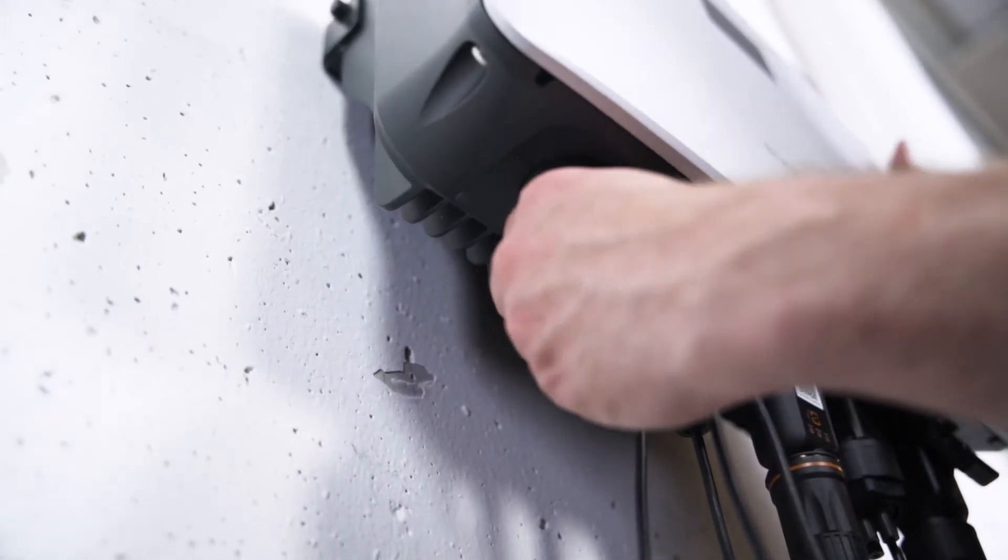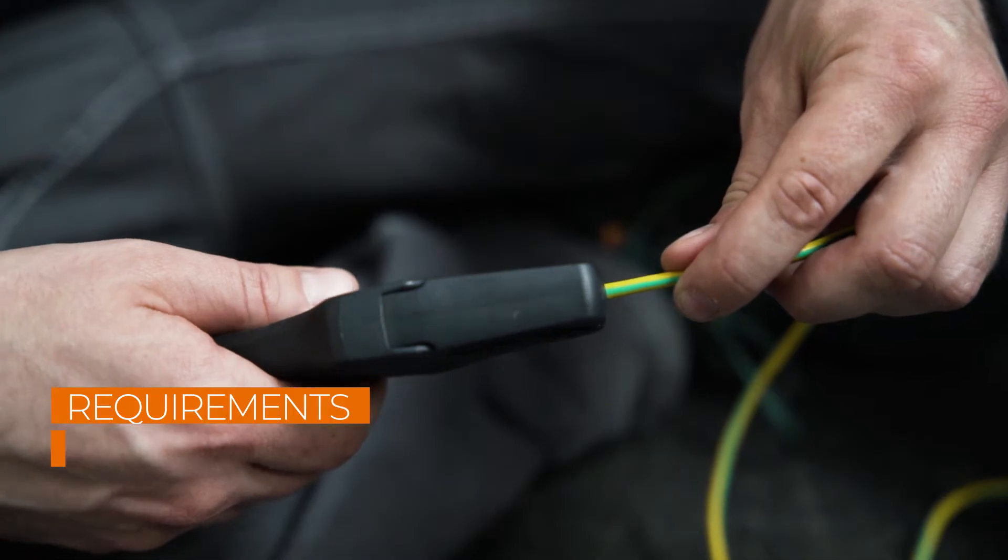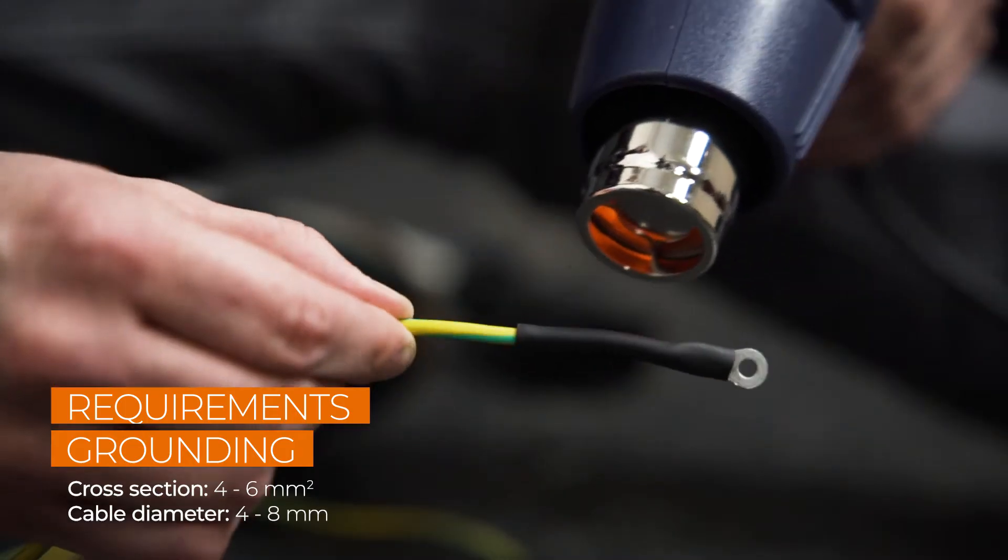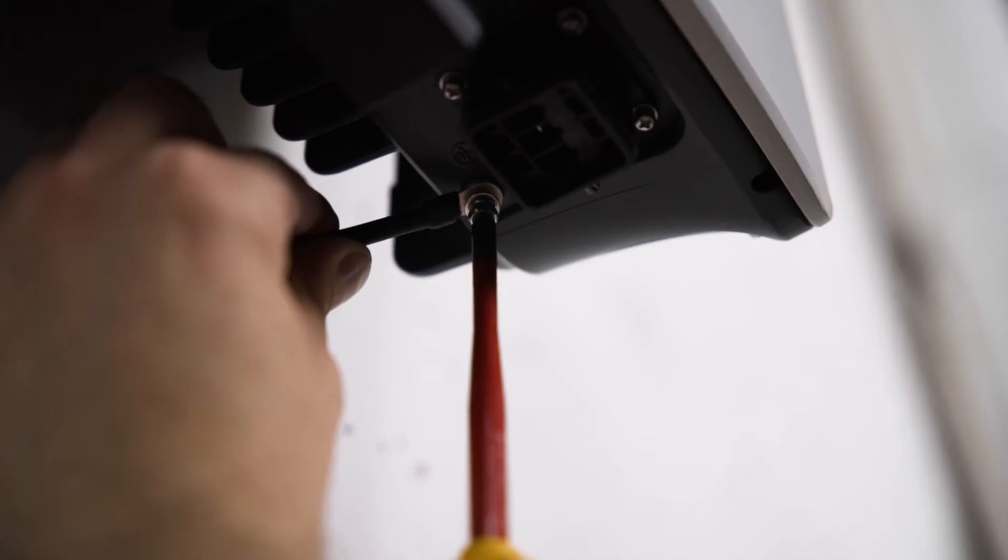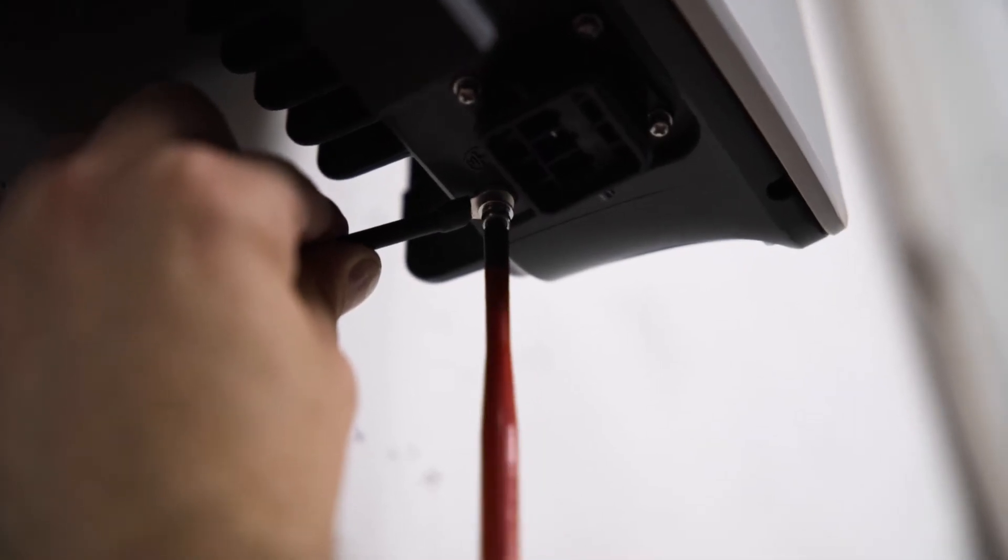Furthermore, you have to set the DC switch at the bottom of the inverter to OFF. Now, let's connect the inverter to ground. There is a grounding terminal at the bottom of the inverter. Connect it to the general grounding of the house.